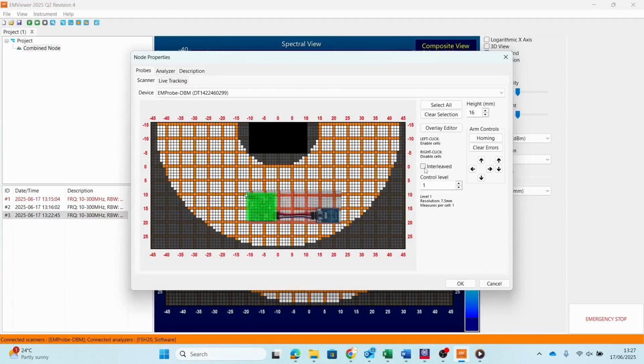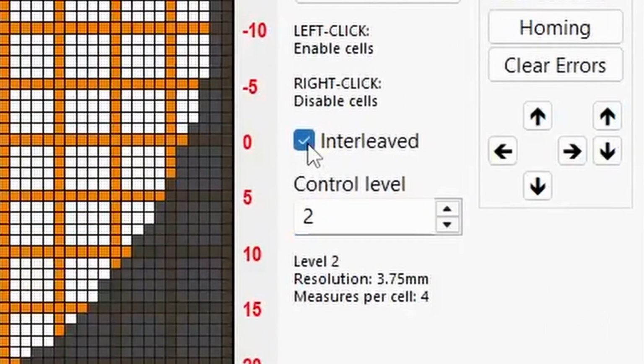Now, we will perform a scan with the interleaved mode, which eliminates the probe's blind spot by performing a second scan with the probe rotated 90 degrees. We will also use control level 2, which will perform more measurements per cell to scan at a resolution of 3.75 millimeters.